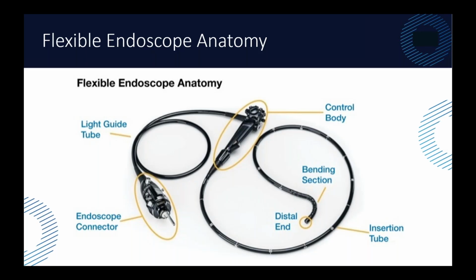So it's significant. And then after that, you get into the insertion tube, which is just the black tube, and it's usually lettered or stenciled with distance. This is a much more robust area of the probe. It's got multiple layers of vinyl on top of a chainmail sleeve. And in that sleeve are all of the wires and instrumentation needed to go down to the tip for whatever need, be it ultrasound or endoscopy. So we don't see a lot of insertion tubes cut. We do see them bitten. Typically, this will be somebody who doesn't have a bite guard in and can get it under a molar. And you'll see some pictures. They can just crush it. They can't really cut through it. I don't think anybody is strong enough to cut through that vinyl with their teeth, but they can still crush it.